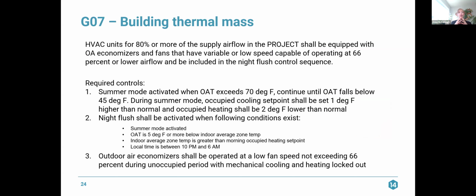HVAC units that supply 80% or more of the supply airflow in the entire project shall be equipped with outdoor air economizers and fans that have variable or low speed, capable of operating at 66% or lower airflow, and be included in the night flush control sequence. So in order to comply with this credit, you have to have central systems, or individual furnace type systems, that have outdoor air economizers, and they have to have either EC motors or VFDs. Then there are required controls for this night flush. So not only do we need the mass interacting with the interior space and the interior ambient air, but we also need to be able to flush out the building at night.